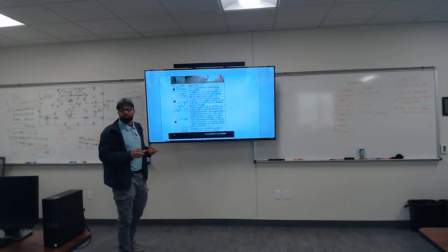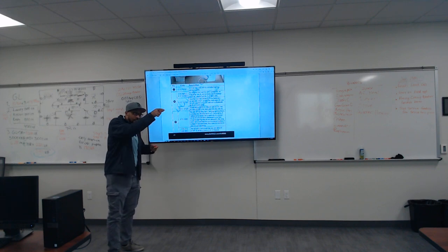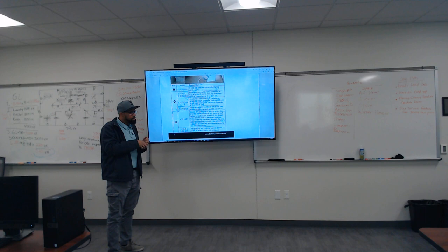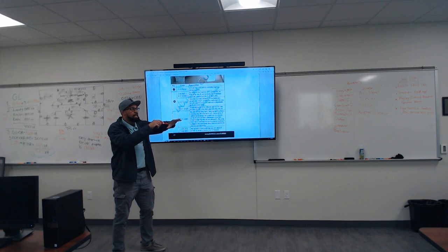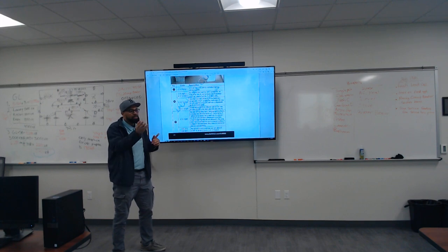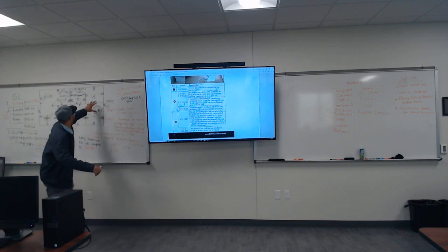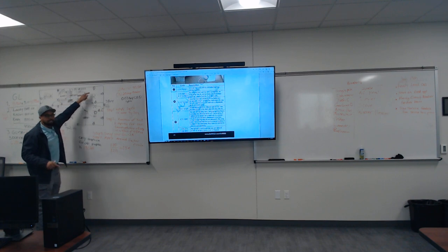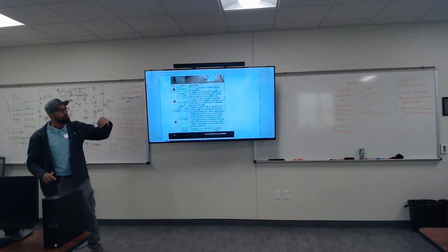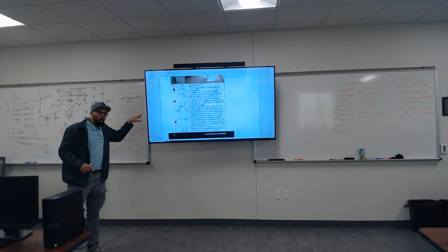But if you have two bathrooms, guess what? You need two breakers, one for each bathroom. Let's say we have a master bathroom and the other hall bathroom. What you could do is put the master bathroom on plugs only, and then have another circuit breaker, probably with all of the lights in this vicinity. The lights of that bathroom, if there is more than one bathroom, can go along with the other lights. That's basically what they're saying. But since you have one bathroom, you can put the plugs and lights on that circuit breaker.